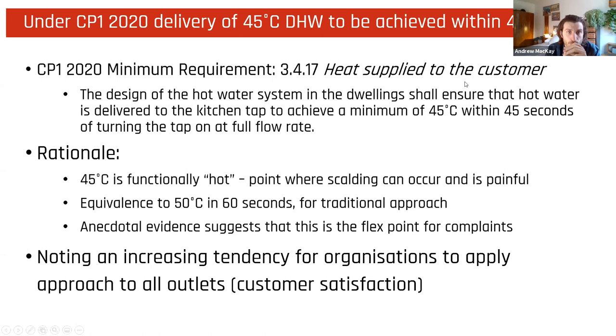So we now have under CP1 2020 a requirement of delivery of 45 degrees domestic hot water to be achieved within 45 seconds. That's minimum requirement 3.4.17. And the rationale for this is, as Andrew showed in his slide earlier in that table, actually 45 degrees is functionally hot. It's the point at which scalding can occur, and it'll take a long time, but it is actually painful to touch. So from a functional perspective, that's actually hot, and that's a sensation that a customer will be getting. Coming back to the traditional approach, it's more of an equivalence to 50 degrees in 60 seconds, and anecdotal evidence suggests that this is the flex point for complaints.